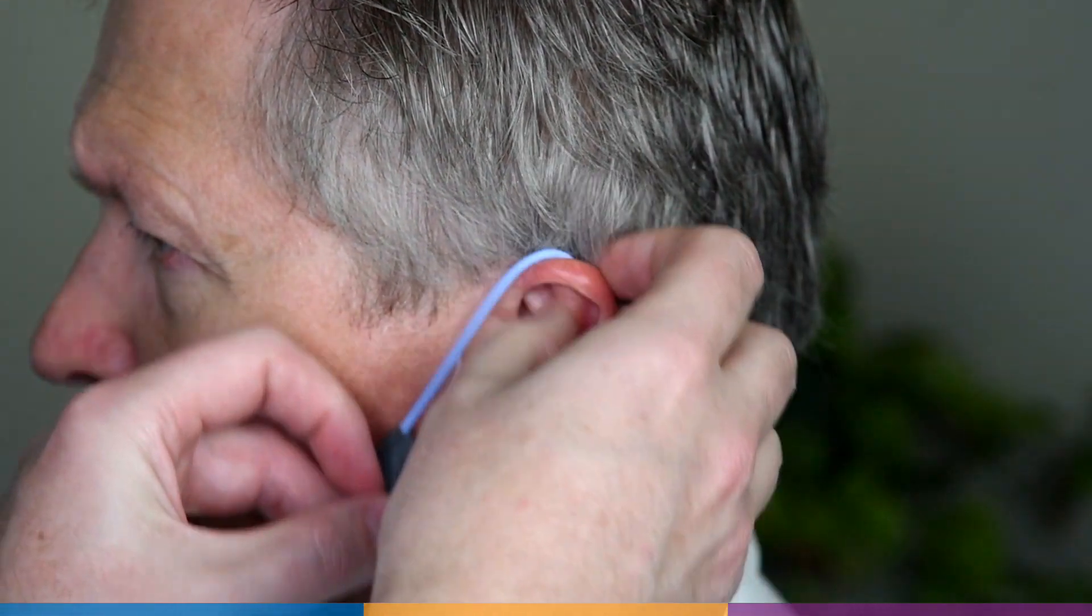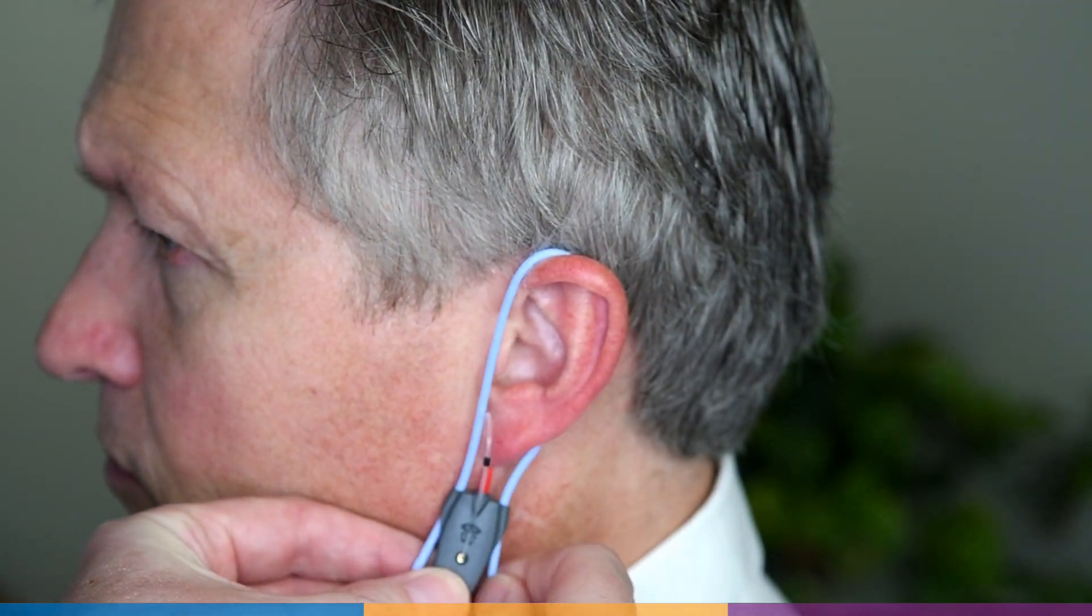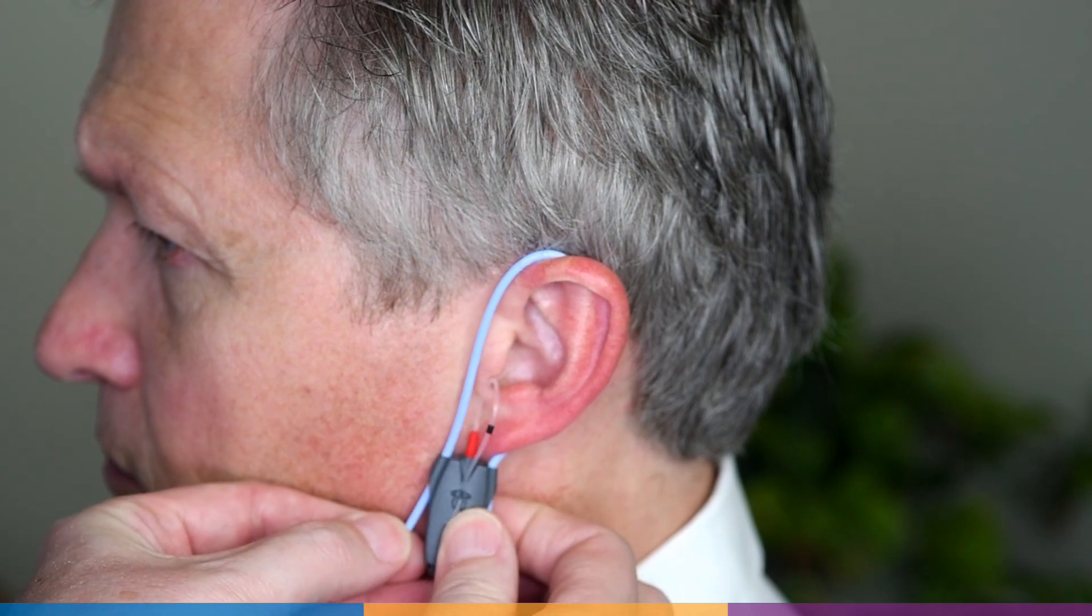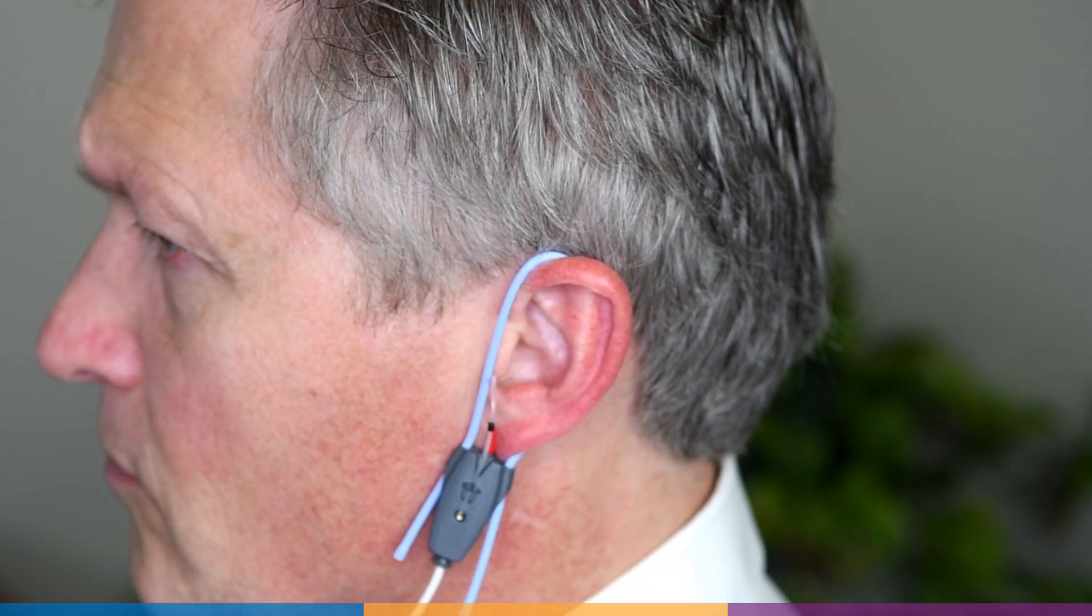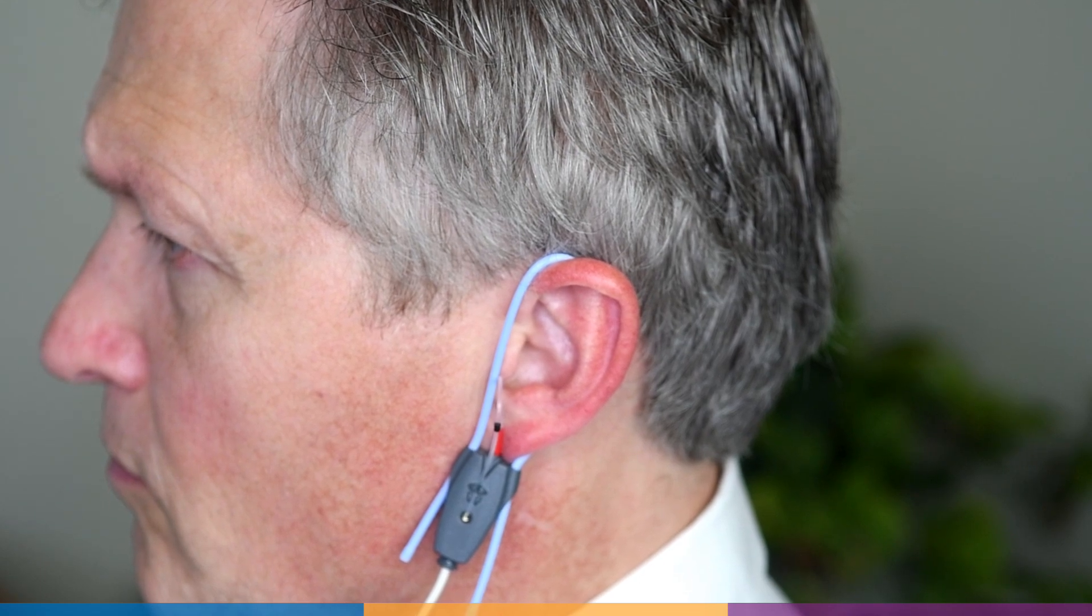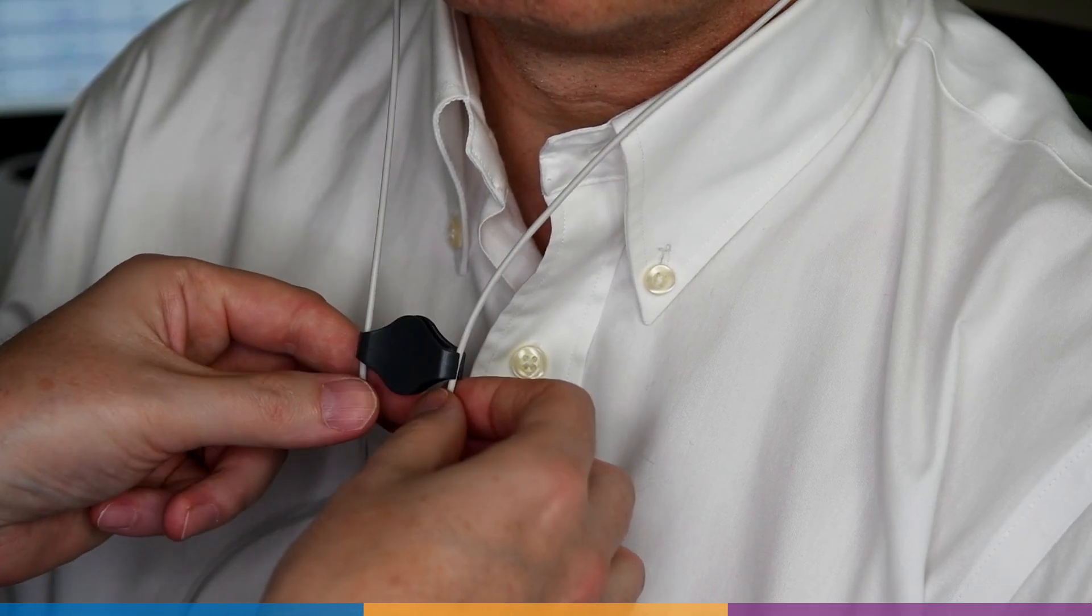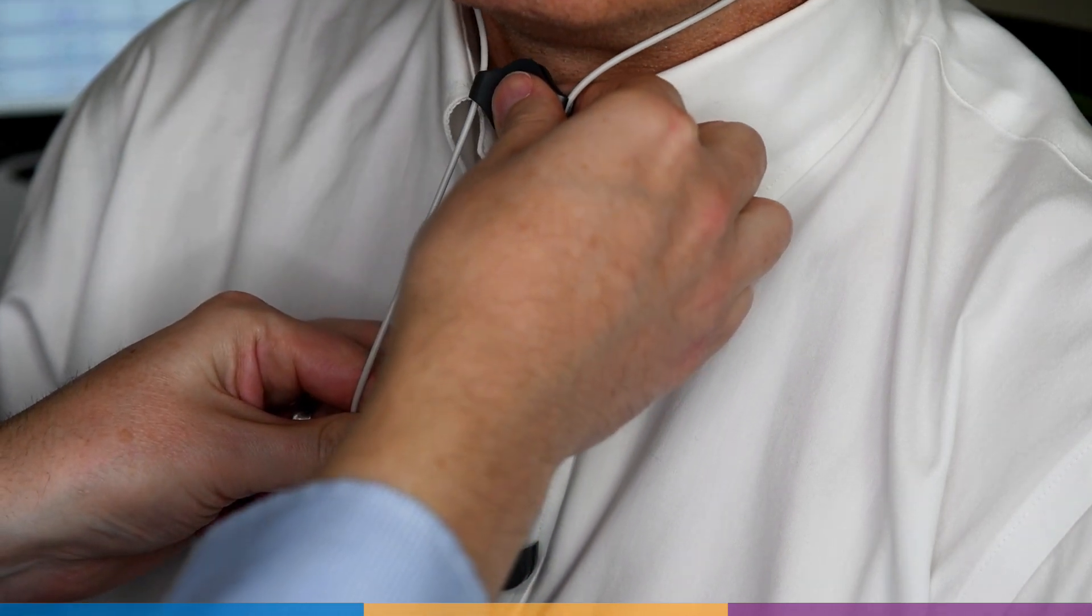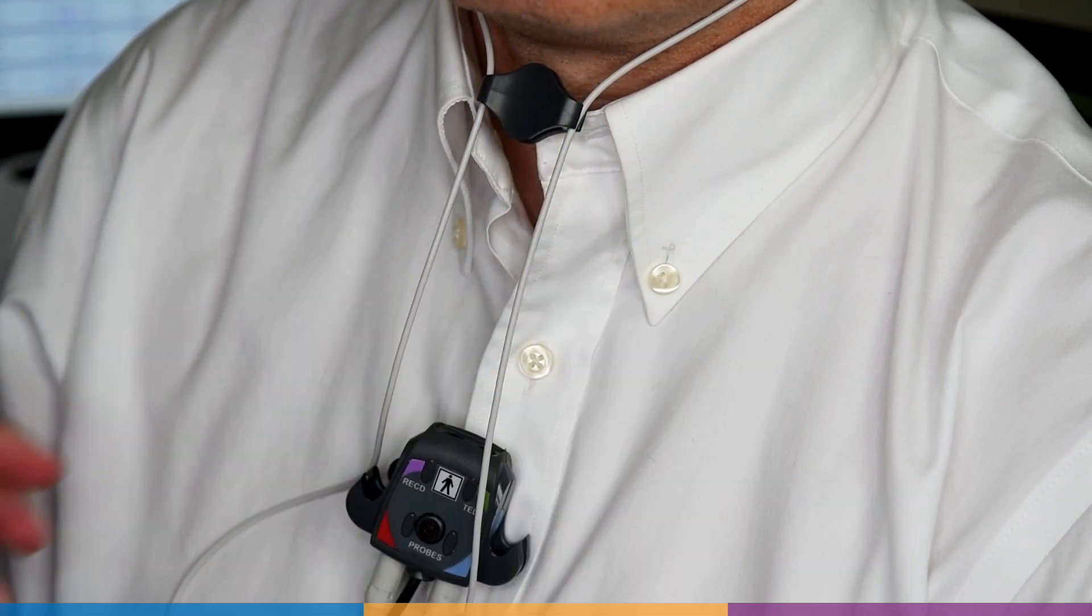The probe dock needs to be positioned so that the probe microphones will easily reach the patient's ears. Hang the probe module on the ear as shown. The reference microphone should face outward. Adjust the blue or red lanyard until the probe module is snug against the head at cheek level directly below the earlobe. Use the probe cable's adjust clip to take up slack in the cables where necessary to ensure correct positioning.